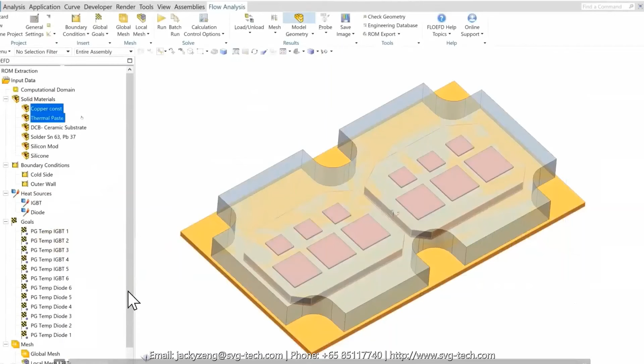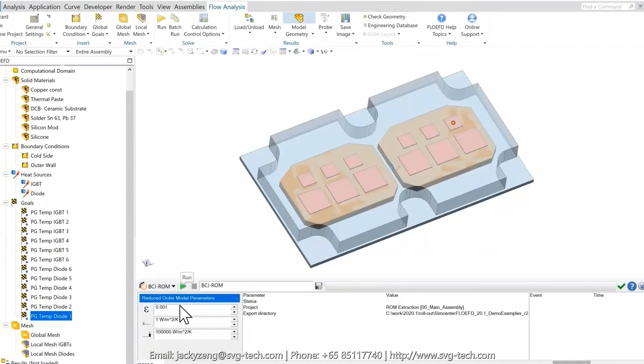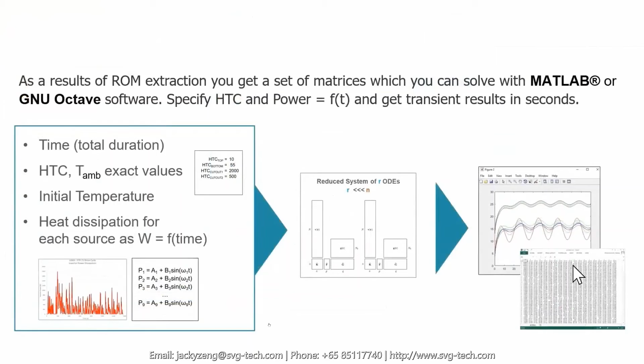So you can see there are materials as well as hot and cold side applied, and you have the IGBT boundary conditions for the heat sources and some point goals which at the end get you the temperature of the individual components. You extract the ROM where you specify the error, the maximum and minimum heat transfer coefficient, so basically either liquid or gas cooling, and then you create the BCI ROM. This file can then be directly used in MATLAB or GNU Octave. You can see here the files that are getting created. And then MATLAB or GNU Octave is solving that based on the boundary conditions that MATLAB and GNU Octave apply to it.